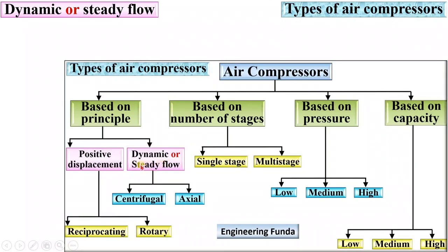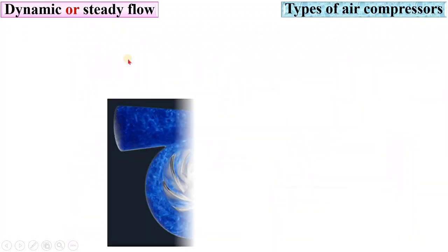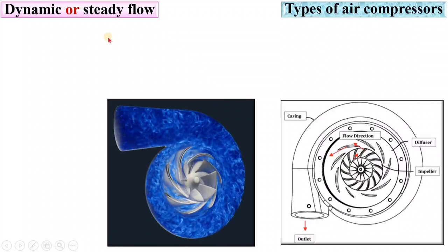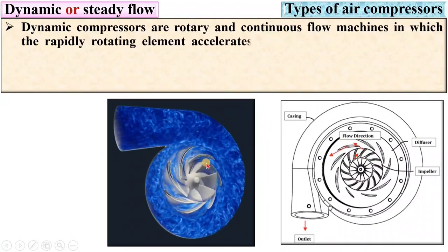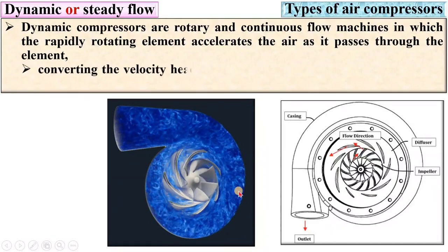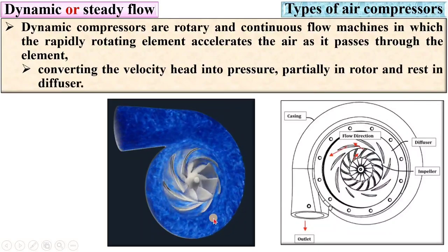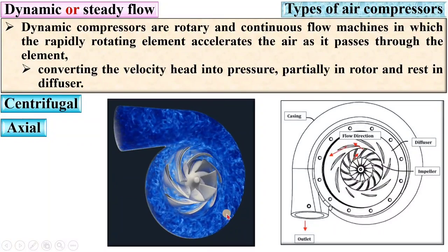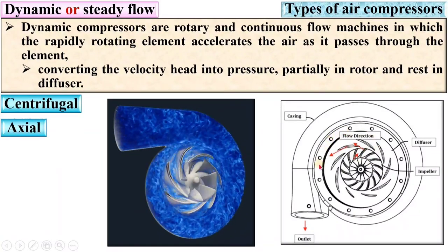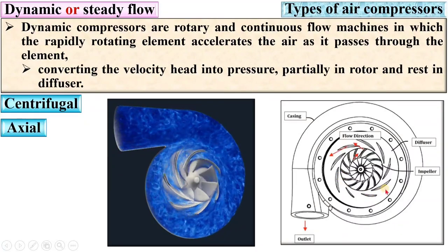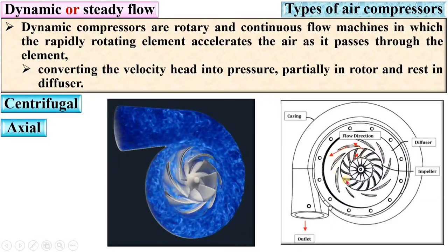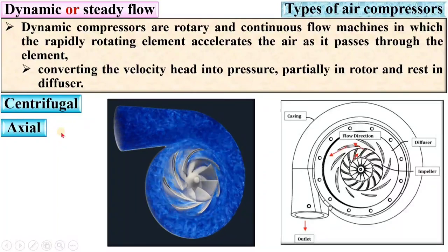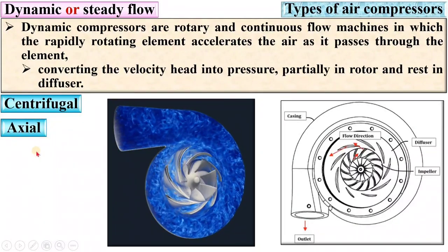Next, dynamic compressor, also known as steady flow compressor. Dynamic compressors are rotary and continuous flow machines in which the rapidly rotating element accelerates the air as it passes through, converting the velocity head into pressure — partially in the rotor and the rest in the diffuser. Pressure is increased due to the conversion of velocity energy.